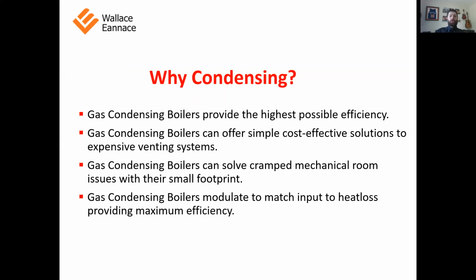And also the modulation is much increased on a condensing unit. On our Crests, you can get 25 to 1 turn down in some of these units. So when you can turn down to 4% load to match what's going on in that building, you can be sure that you are using your resources efficiently and effectively.